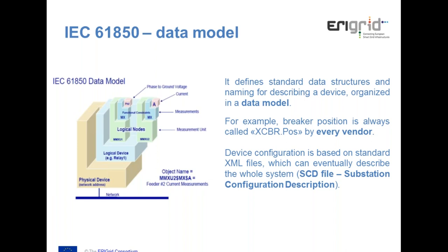This data model can be expressed through the use of standard XML files, and for example, a whole description of the substation automation system can be realized by using a particular file, which is called an SCD, substation configuration description. And in this way, it is possible to specify, in an interoperable way, the information related to a particular substation automation project.